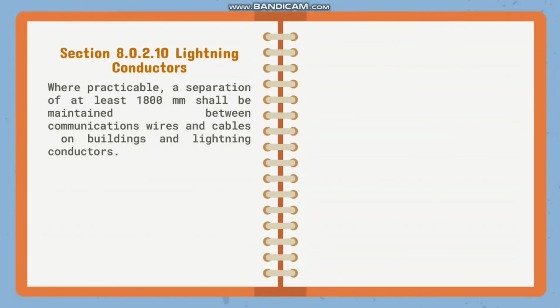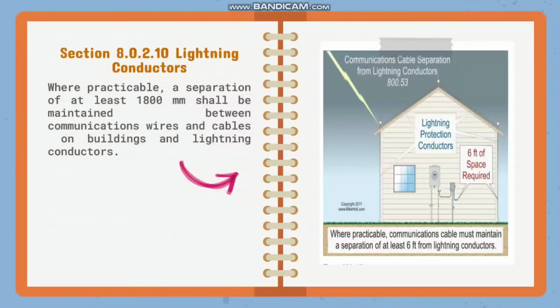Next po is section 8.0.2.10, lightning conductors. Where practicable, a separation of at least 1,800 mm shall be maintained between communications wires and cables on buildings and lightning conductors. So, kagaya po ng nasa illustration is dapat po ma-maintain yung at least 1,800 mm or 6 feet na distance or separation ng communication wires and cables at lightning conductors.